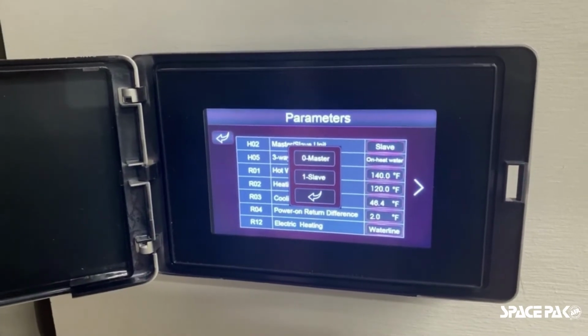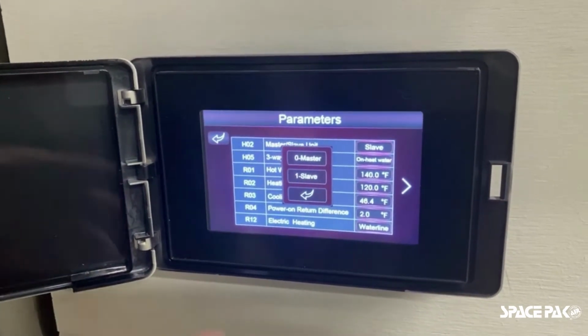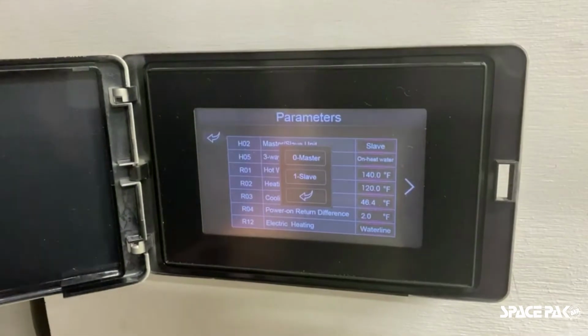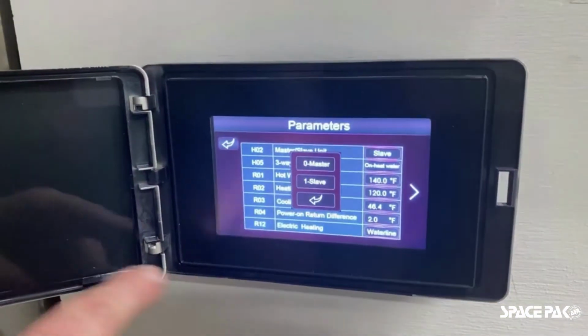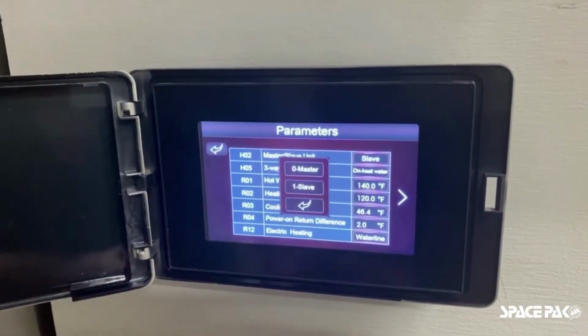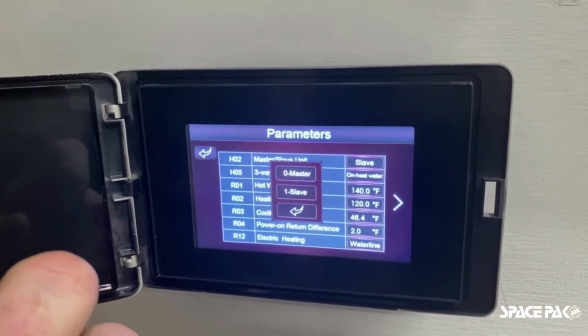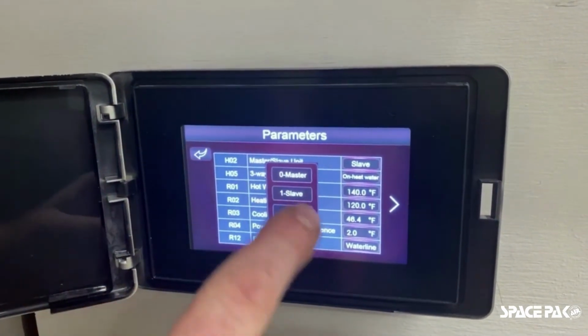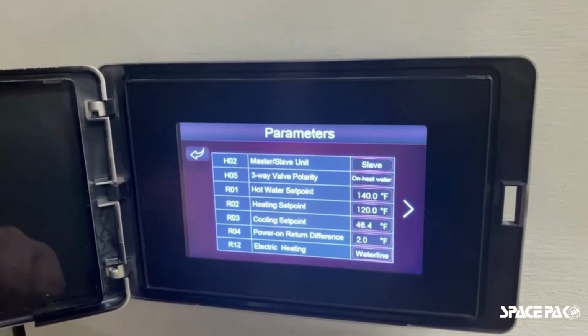Now, when it comes factory, when it comes right from us, when you initially turn that unit on, it will absolutely be in master mode. You'll have to go in, click on the master slave H02 parameter setting and change it to the slave mode.